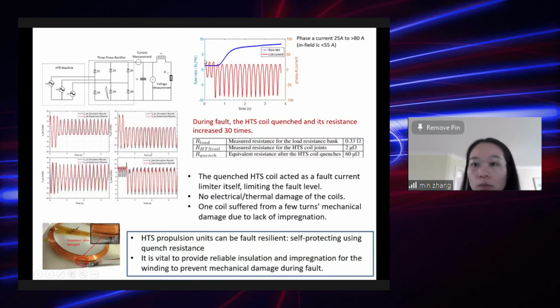So this part shows you the normal operation of the machine, and then this is when the coil actually quenches. So for the phase A coil, the current goes above 80 amps, which is about 25 amps higher than the in-field critical current, which means the coil actually quenches during the operation. And then you will also see a dramatic increase in the boil-off rate of nitrogen inside the measurement chamber. So all this large current will be pushed into the copper stabilizer of the HTS coil. And then we also did a simulation in MATLAB and found consistent agreement between the measurement, shown in the red one, and the simulation, the black one.